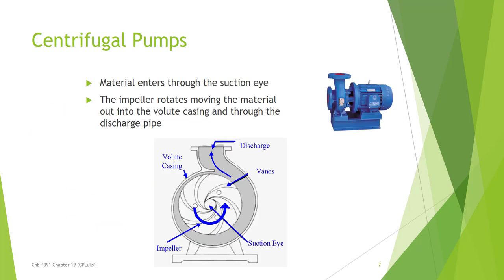Centrifugal pumps are going to be the mainstay of what we do in a chemical plant. Material comes in through the suction eye into the rotating impeller, which throws the material outward — that's what happens when you rotate equipment. This increases the pressure and kinetic energy, and the fluid is then collected on the discharge side and sent on to the next location.